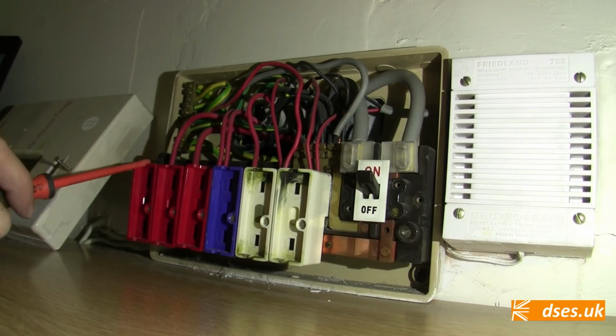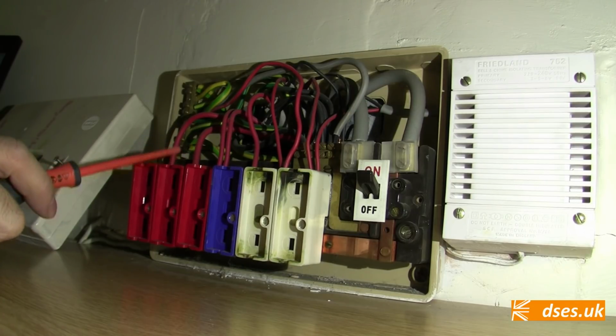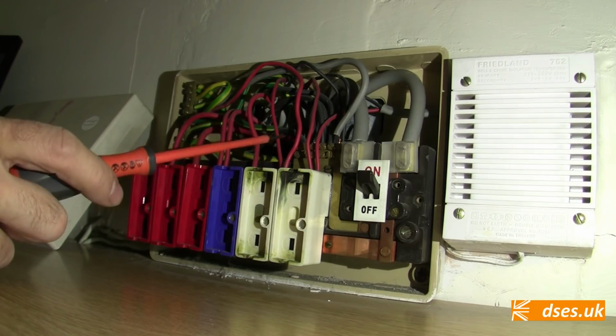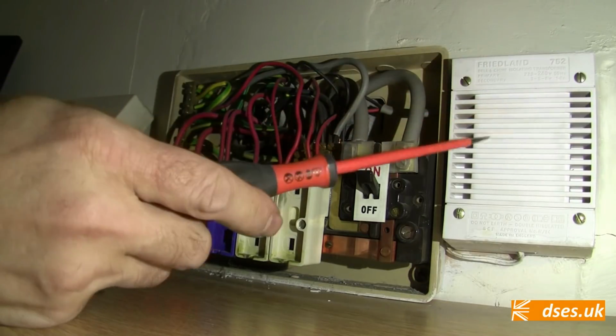We've got 4 lighting circuits, it appears. One of them's going to be the outside light. 6mm cooker, that's got to be the shower, hasn't it? Yeah. 6mm. Socket ring, immersion heater, 2 wires for the lights. I reckon one of them is perhaps the outside light. 2 wires on this lighting circuit, one of which is going to the doorbell. Yeah. However, there is a wire coming off the doorbell, but there's no doorbell out there, is there?